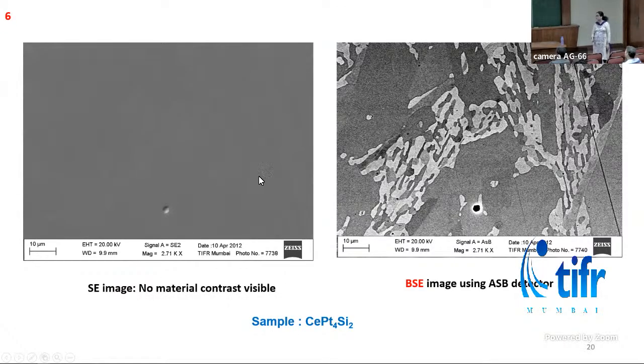I mentioned Z contrast imaging using SEM. This is such a sample of cerium platinum 4 silicon. By looking at the topography of the sample, we feel that the sample is homogeneous. But when we image the same sample using an ASB detector, that is an angle selective backscatter detector, we see a very colorful sample, meaning the sample is not homogeneous. The bright regions are made up of elements which are high Z, or high atomic number, and the gray regions are made up of elements which have low atomic numbers. This can be confirmed by doing a point mode EDS analysis on the sample.